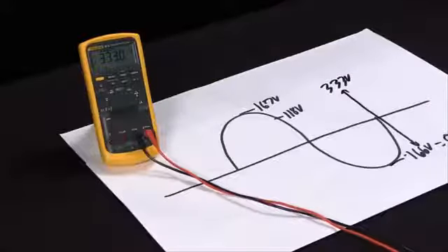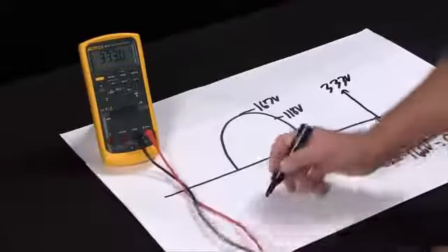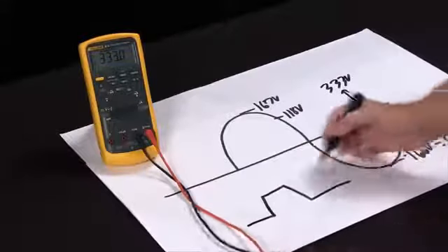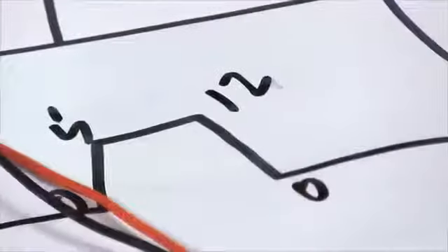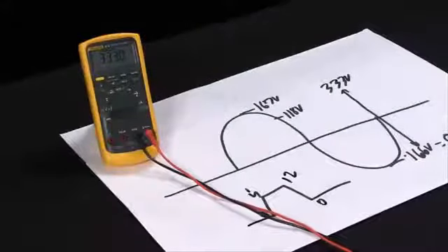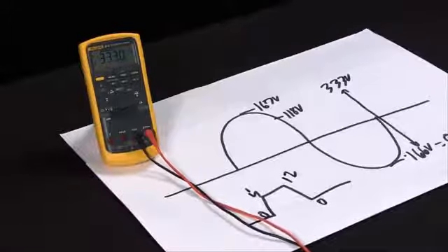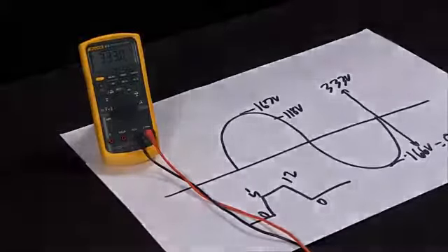For a sine wave this might not be so handy, but when you're working on a square wave coming off an encoder, what you really want to see is: is this 0 to 5 volts, is it 0 to 12 volts? By having that relative mode and the peak min max, you'll be able to check your square waves a whole lot better. So that's how we can use the relative mode on the Fluke 87 to troubleshoot a number of different situations that we're working on.